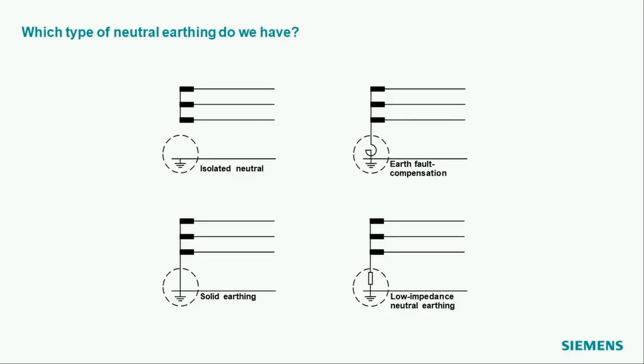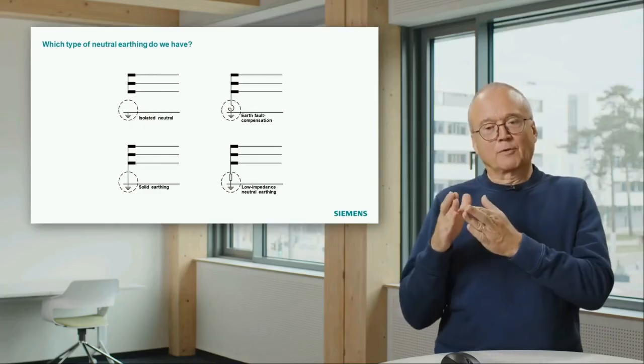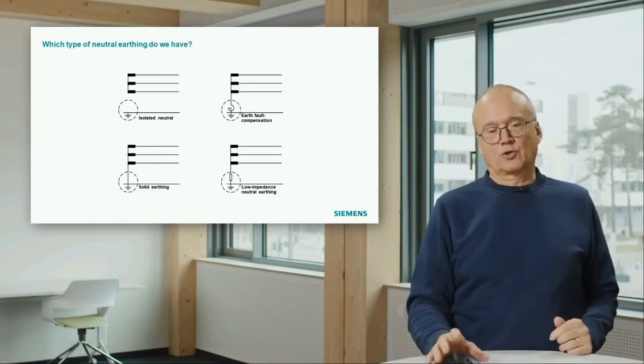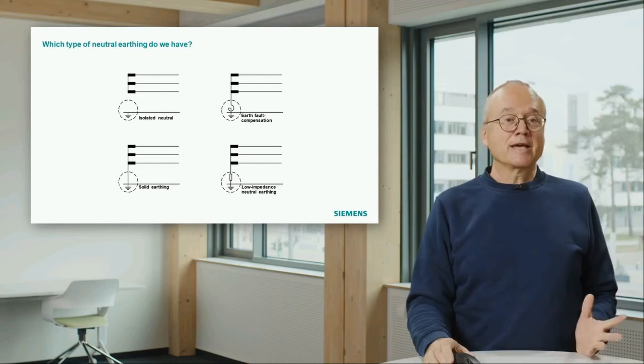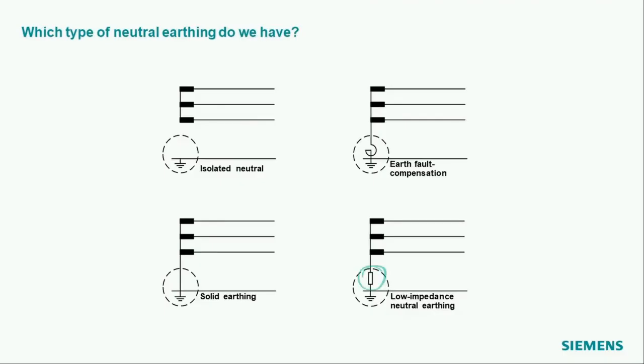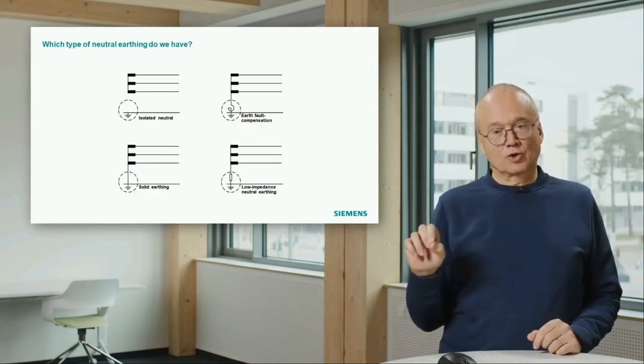What does that mean? That means if you have a short circuit, a single phase short circuit, or a connection to ground, which is the most probable type of short circuit, then you have really a short circuit loop here. With this type of fault, connection of one phase to ground, you have a short circuit with a big short circuit current. If you want to reduce the short circuit current, you can add a resistor here in the star point. If you again imagine this connection to ground and look at this short circuit loop, you now have the resistor in this loop. And that means by this resistor, you can limit the short circuit current.